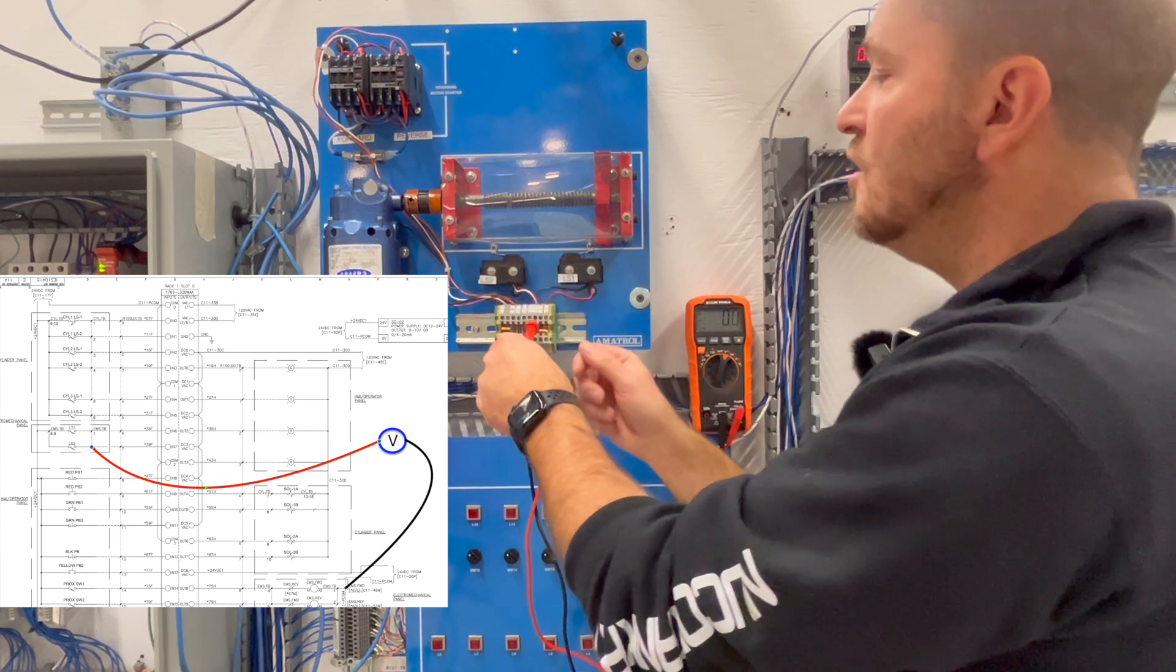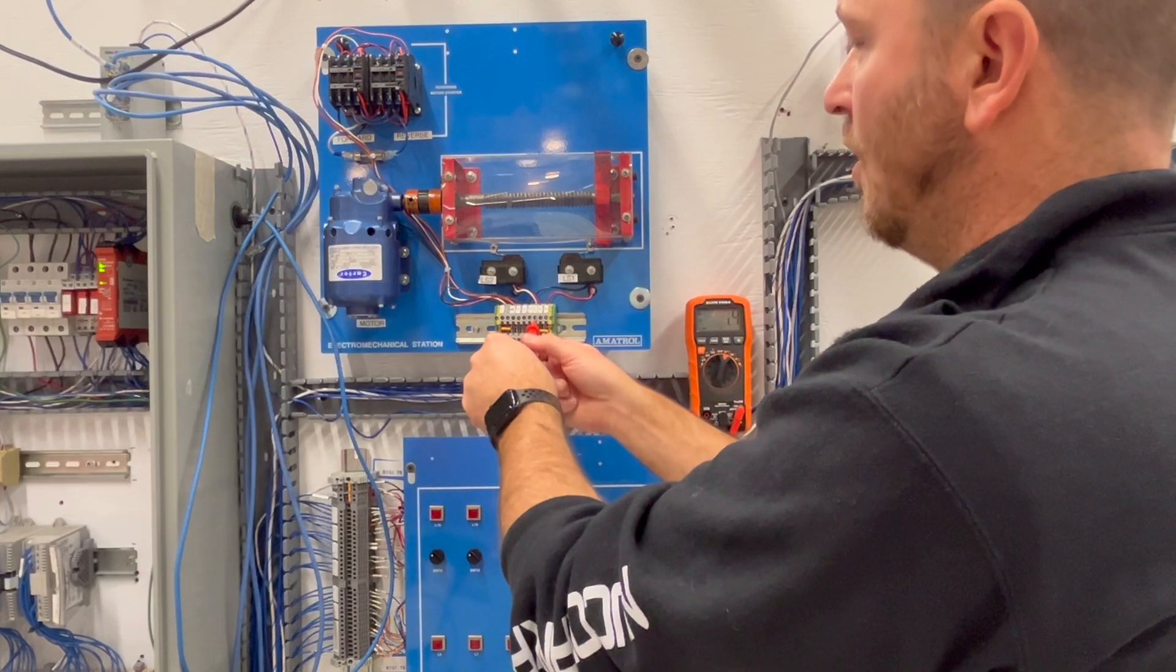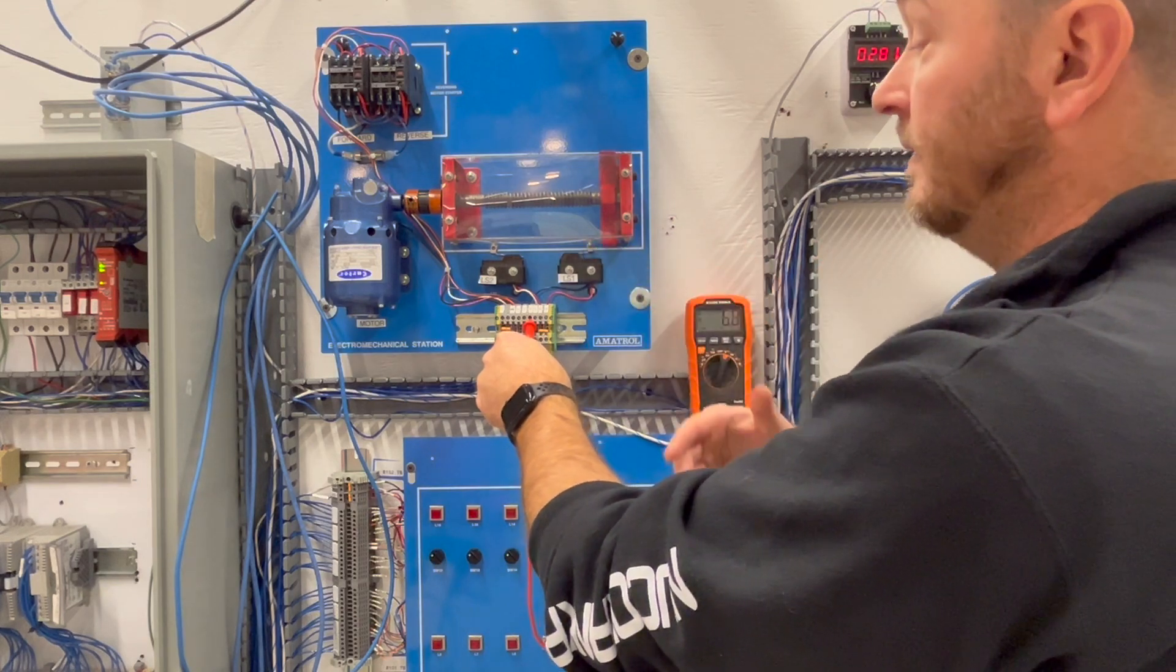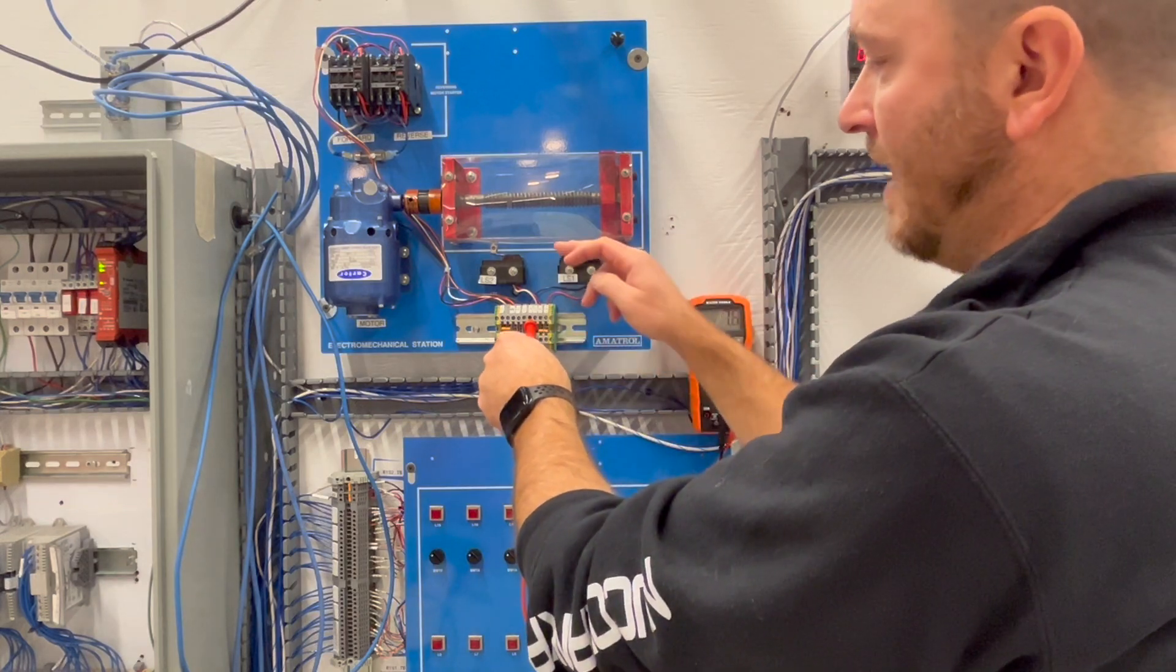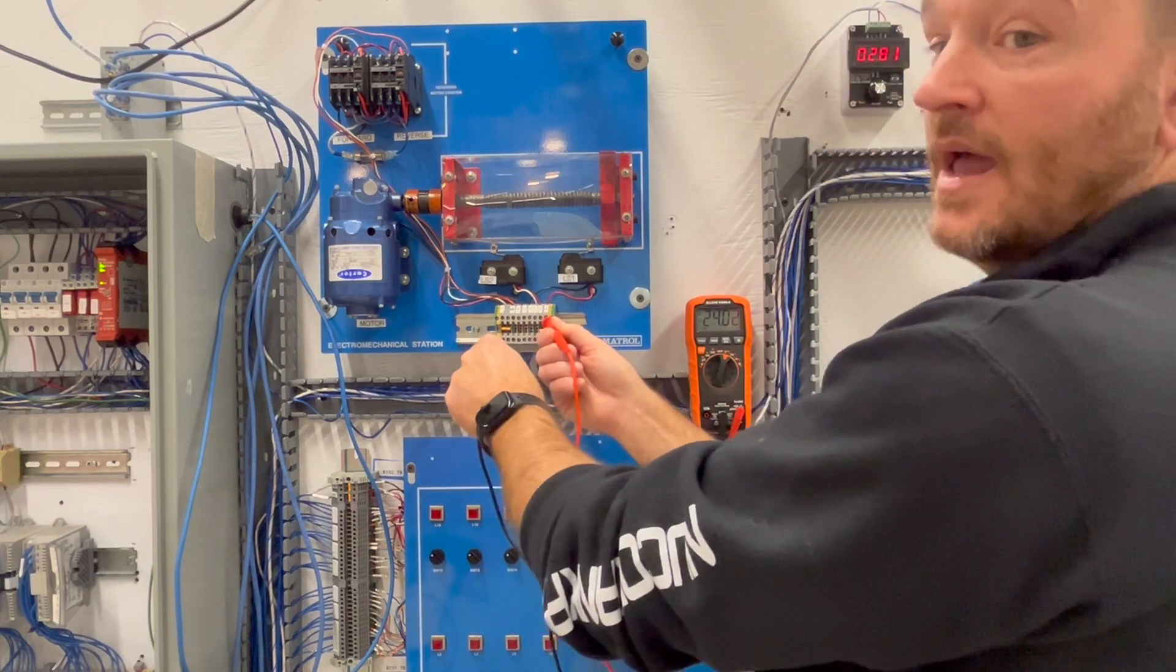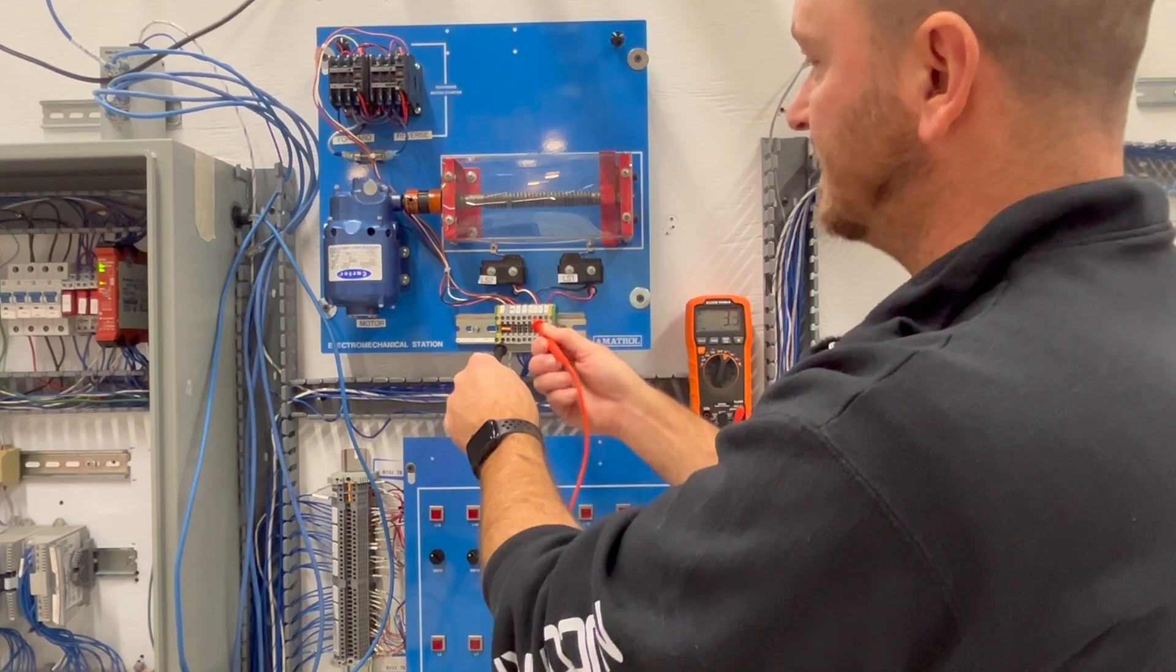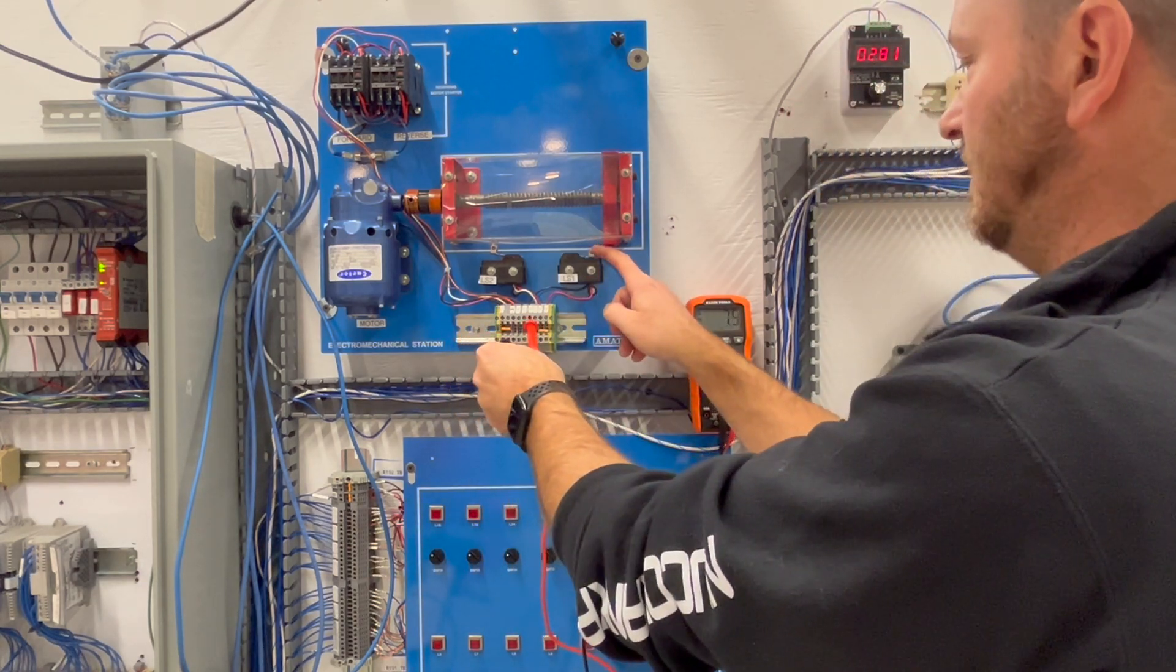Okay so what that tells me here is that there's an issue with my input here, whether this be a push button or anything else, my LS1, something's going on from here out. So what I want to do, because I know I have 24 volts going into the switch, 24 volts is coming in but it's not getting down to here when the switch is activated.